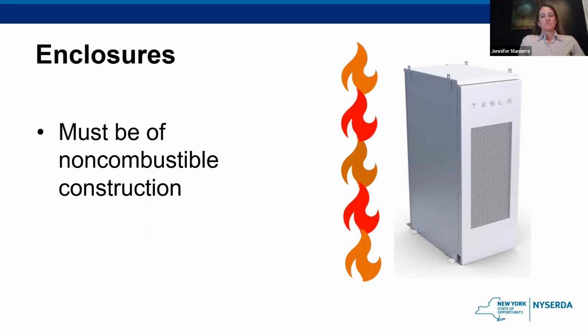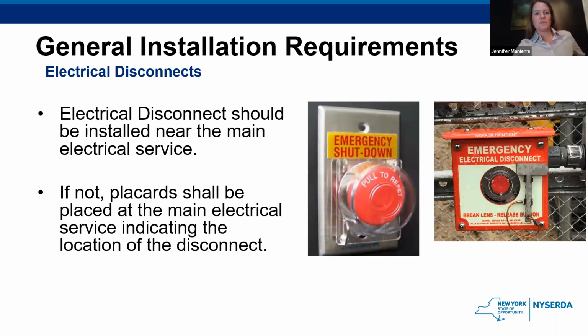Okay, might seem obvious, but one of the major code requirements is that all of the enclosures for these energy storage systems need to be non-combustible. There are some general installation requirements. There should be an electrical disconnect installed near the main electrical service. And if that's not possible, there needs to be some sort of signage placed at the main entrance telling you where that disconnect is located.